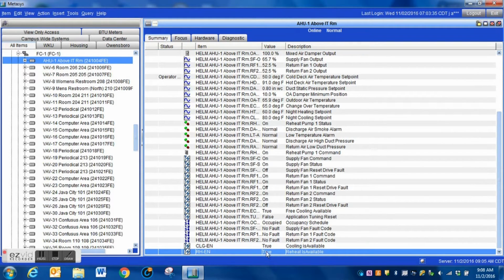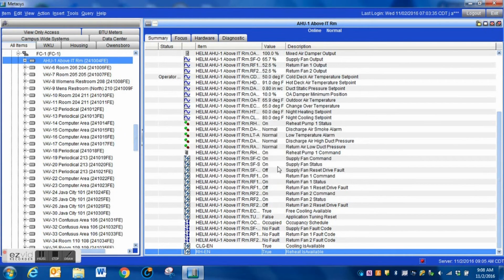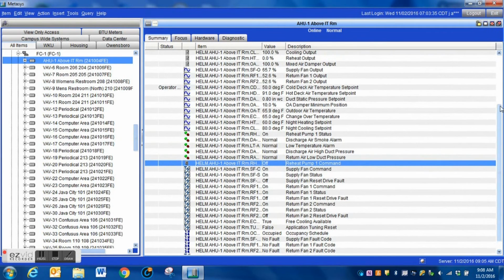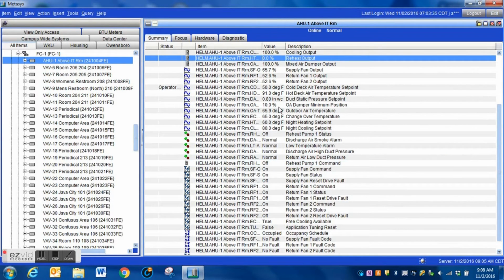So what we need to do is to set up some logic that will turn on and off this availability automatically. And we're going to be doing that in LCT. You can see here when I disable the heating availability that it shuts the pump off, it closes the valve, and that's exactly what we want it to do.